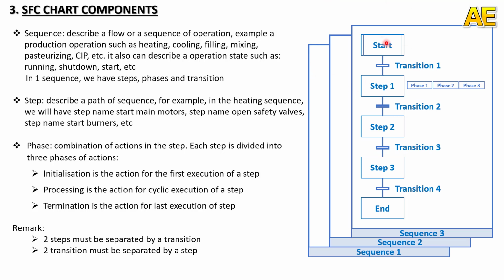And coming back to the chart here, you can see this is the start step and this is the end step. Between 2 steps here we will have the transition. This is the condition to pass from the previous step to the next step. And in the step we will have the phases, 3 phases here. Okay, the phases I explained already.